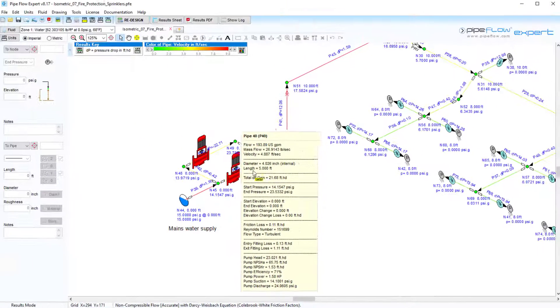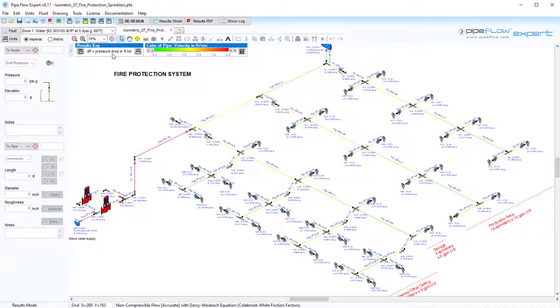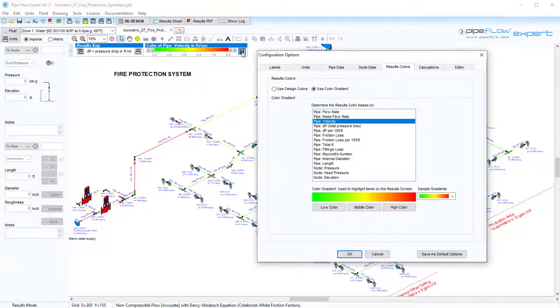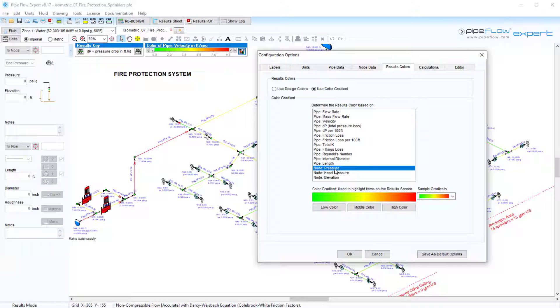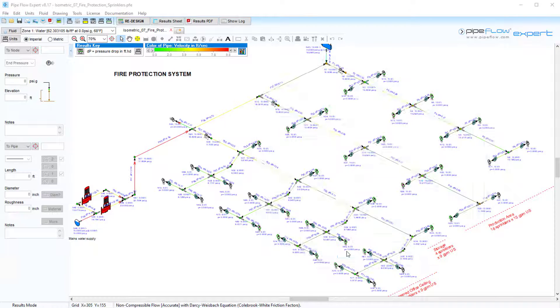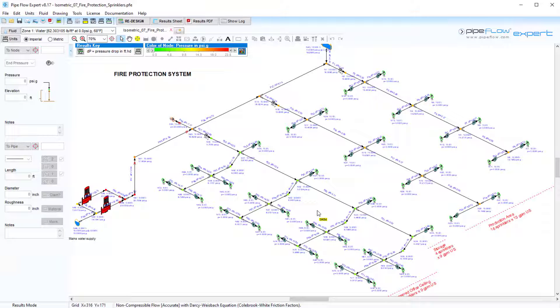The pipes on the results drawing are displayed using a color gradient to highlight the particular item of information such as the velocity in each pipe. The color gradient can also be switched to applied to node data such as the pressure at each node. Coloring the results helps the user visualize the system's operating conditions and aids in highlighting potential problem areas.